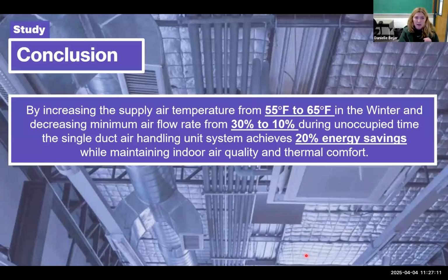So just to reiterate, to wrap everything up, in conclusion, by increasing the supply air temperature from 55 degrees Fahrenheit to 65 degrees Fahrenheit in the winter and decreasing the minimum airflow rate from 30% to 10% during unoccupied time, so only making changes to controls, no changes to hardware, the single duct air handling unit system achieves 20% energy savings, and we maintain indoor air quality and thermal comfort.